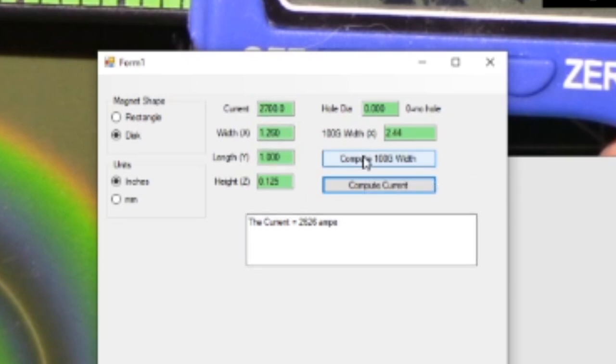But the other thing you could do is if you had know your current magnet's current, you can tell it to compute what the diameter would be, where the 100 gauss distance would be. And that comes to 2.466 inches. Again, if you put it in millimeters, it's 62 millimeters. So yeah, this thing converts the units for you too. But it sometimes doesn't round everything perfectly.